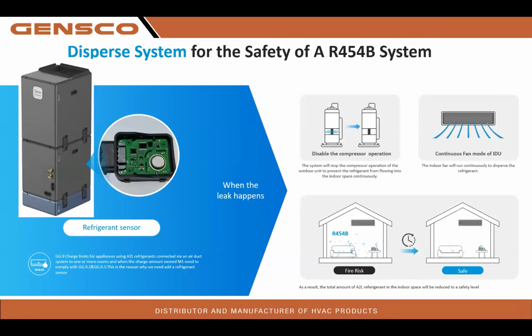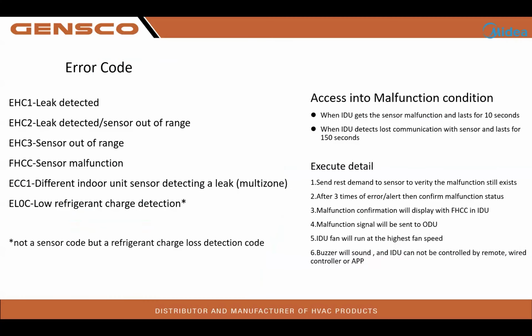Refrigerant leak detector scenarios, we've already discussed it. In the event we go into a mitigation event, we're going to kill the outdoor unit, bring on the fan and mitigate the air. There's a look at some error codes that are common in the event an error pops up. EHC1, leak detected. EHC2, leak detected, sensor out of range. So EHC2 could be that we are in a mitigation event, or that the sensor is out of range.